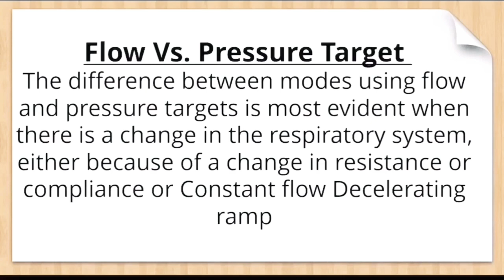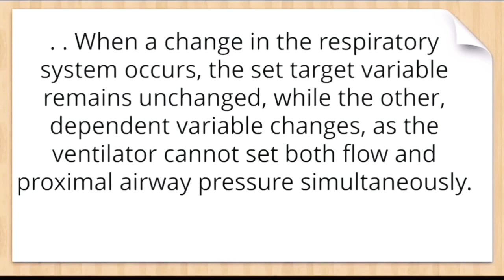Either we have kept target as flow or pressure. If we have kept flow as a target, flow will not change. If we have kept pressure as the target, pressure is not going to change if there is a change in the respiratory system, while the other dependent variable changes, as the ventilator cannot set both flow and proximal airway pressure as the target simultaneously.